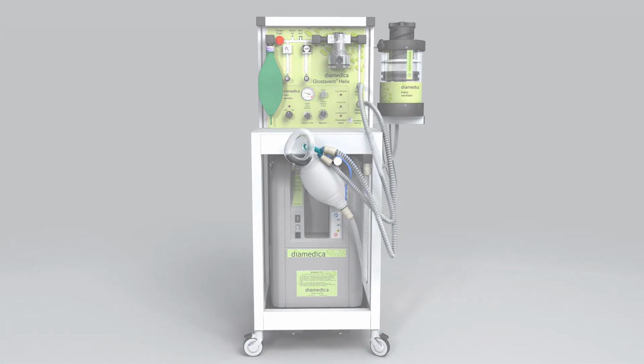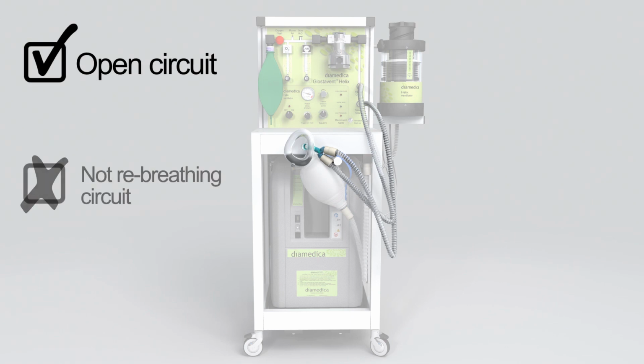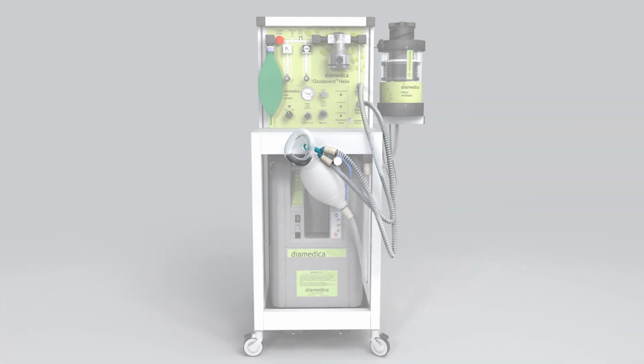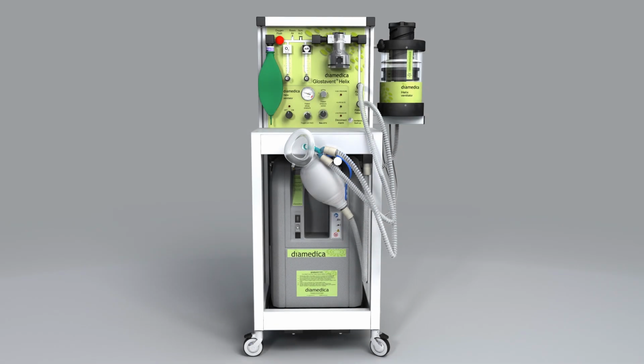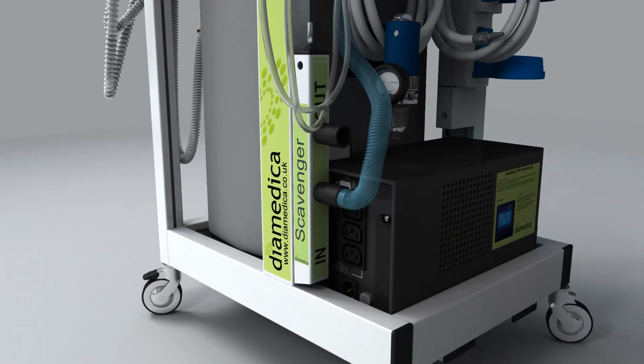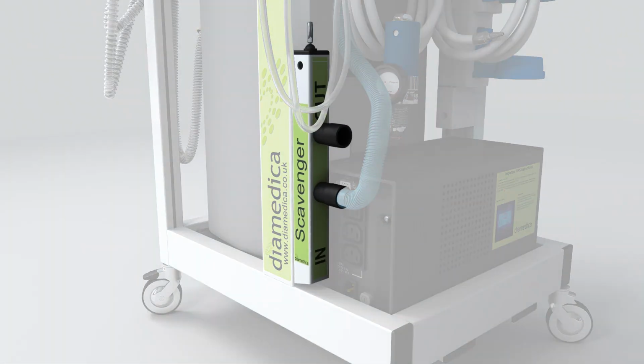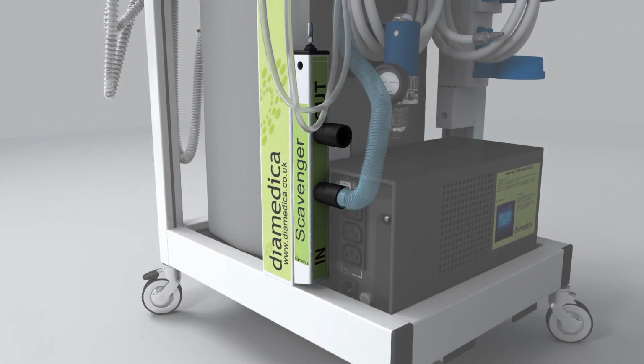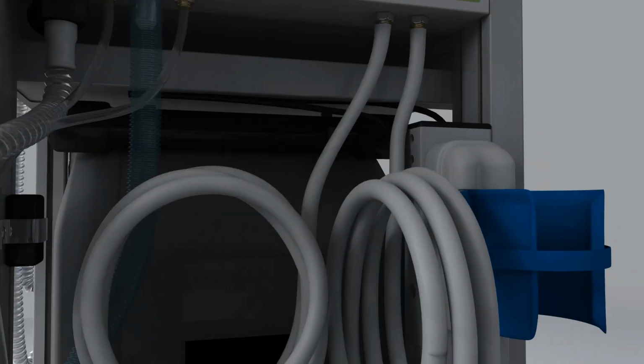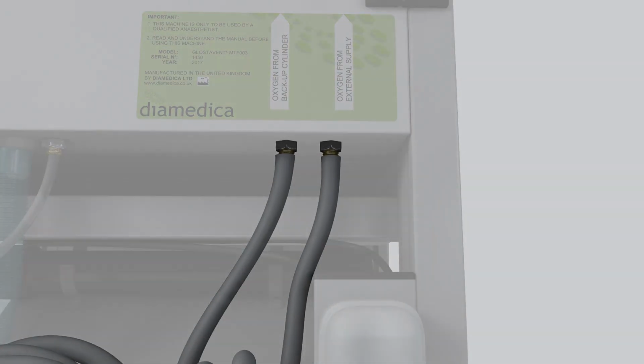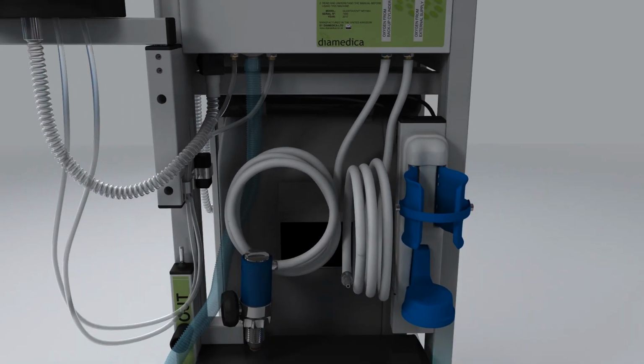The circuit is an open circuit, not a rebreathing circuit, meaning cross-contamination between patients is reduced. This also minimizes the amount of consumables required to run the machine. The patient's expired gases are removed through a built-in scavenging system. There is an oxygen connection fitted to the rear of the machine if required, one with a cylinder connection with bull nose and pin index and another for a wall connection if available.